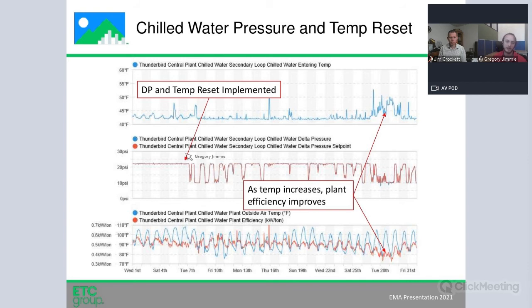The beginning here, this is August in Phoenix. We implemented a differential pressure reset in the first week or so. Previously, they were running at a fixed set point. The most obvious thing you get here is that we start to reset down to the lower end of the pressure thresholds, even in August. We're still seeing 100+ degree days pretty much every day throughout the month, yet we're able to back off on pressure at least half the time, mostly at night. So you'll see some efficiency gains associated with that as well.